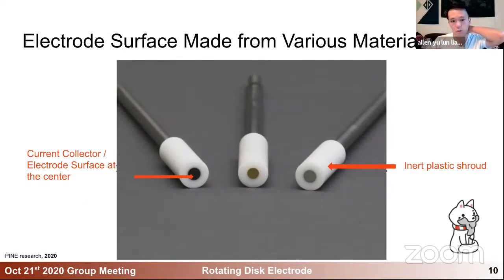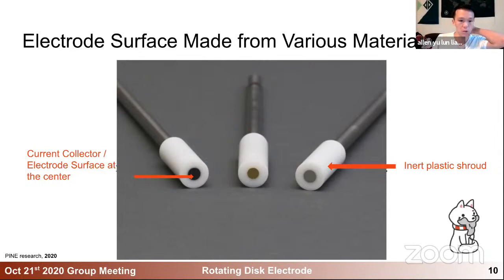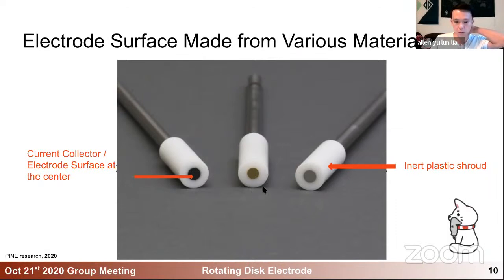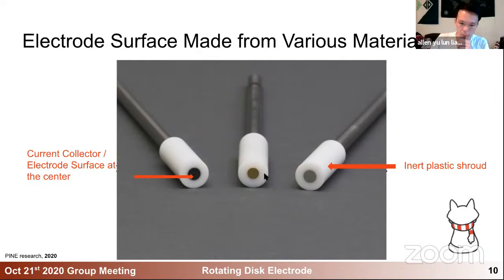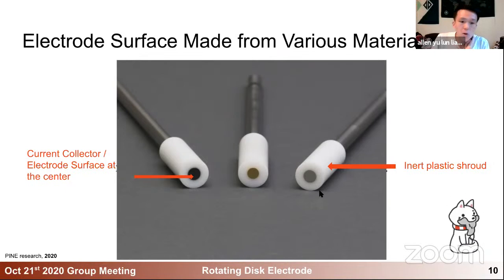The electrode surface can be made from various materials — from carbon on the far left to gold or platinum on the right — depending on what your reaction requires or what the best current collector is for your active material if you're depositing it on the electrode. Surrounding these discs is inert plastic, some PTFE or similar material, which controls the active area and won't react with your electrolyte. You have to choose carefully if you're using organic solvents, as the plastic material may or may not react with your solvent — read the manual and manufacturer's information.